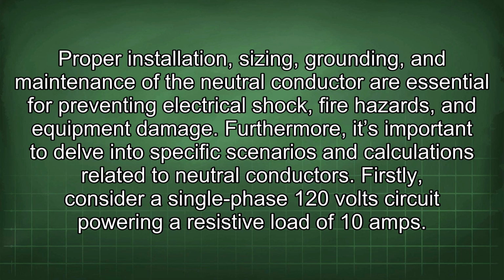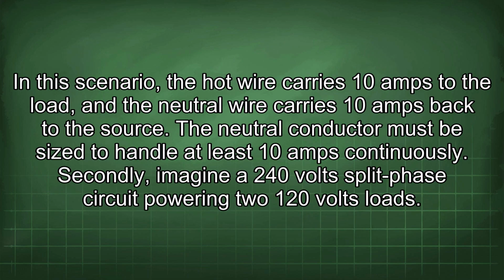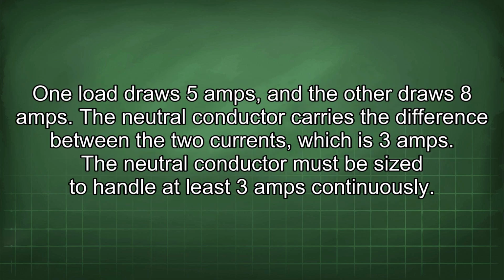Furthermore, it's important to delve into specific scenarios and calculations related to neutral conductors. Firstly, consider a single-phase 120-volt circuit powering a resistive load of 10 amps. In this scenario, the hot wire carries 10 amps to the load, and the neutral wire carries 10 amps back to the source. The neutral conductor must be sized to handle at least 10 amps continuously. Secondly, imagine a 240-volt split-phase circuit powering two 120-volt loads. One load draws 5 amps, and the other draws 8 amps. The neutral conductor carries the difference between the two currents, which is 3 amps. The neutral conductor must be sized to handle at least 3 amps continuously.